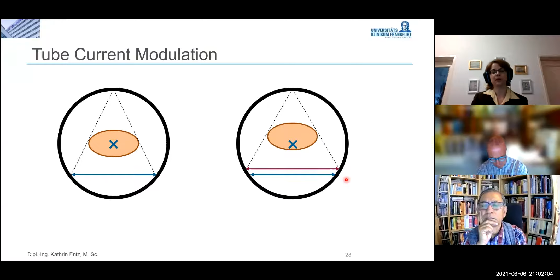In this case, this patient was perfectly positioned in the ISO center and has roughly a diameter of 28 centimeters, which led to a dose of 4.3 milligray as the CTDI. Then that same patient had to be scanned again just a few days later, and you can see here that the patient was not perfectly placed in the ISO center. The table was a bit higher, so that led to a magnification of the patient. So in the image, it appears that the patient is roughly 31 centimeters wide, which means 3 centimeters more.